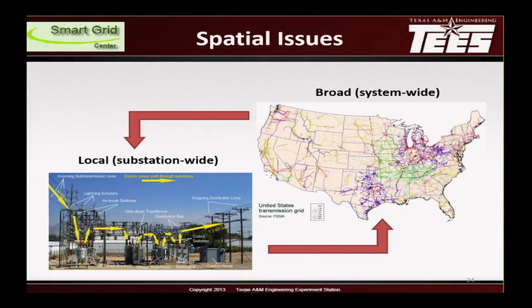By the way, this is a very real problem. If you look at tapped lines, you don't have measurements at taps quite often. Tapped lines are used in some major cities in a utility layout. And to locate the fault with the method that uses measurements from two ends, you don't have measurements from all ends. So it becomes sparse by definition.